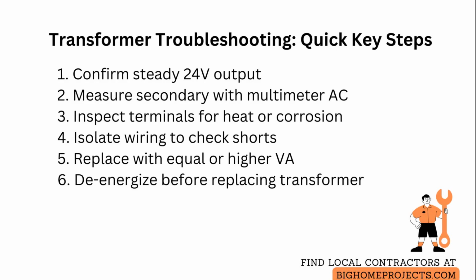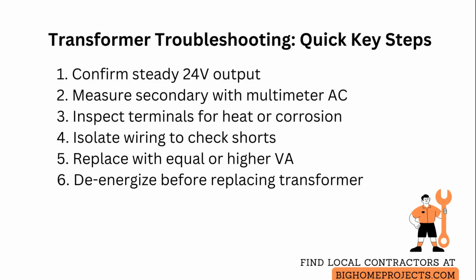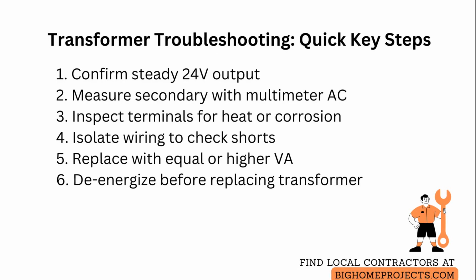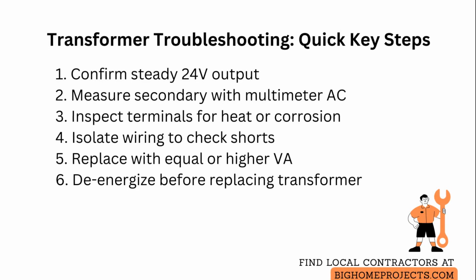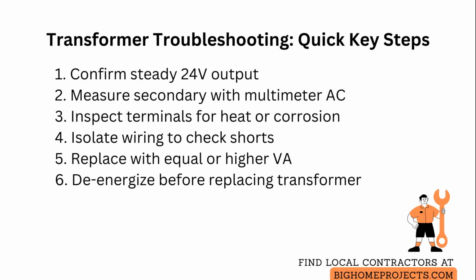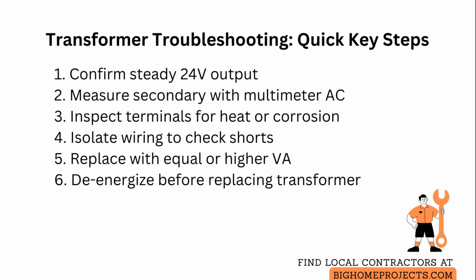When diagnosing blower motor control issues, start by verifying the transformer's secondary voltage with a multimeter set to measure alternating current and compare it to the rated 24-volt output under load. If the voltage is significantly low or fluctuates under load, replace the transformer rather than attempting repairs because internal winding faults can be intermittent and cause hard-to-trace problems.